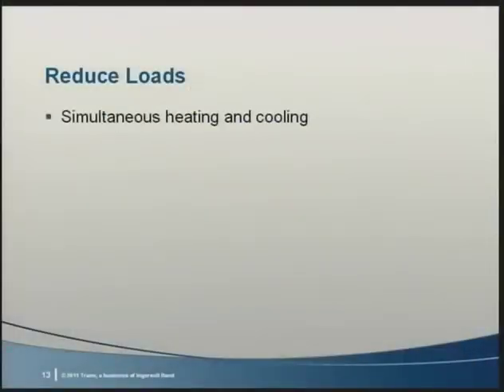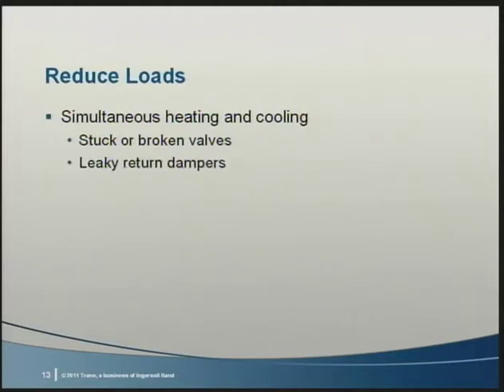Simultaneous heating and cooling is often one reason why a building blows its HVAC budget. When spaces are comfortable, this energy waste can be overlooked. One hidden simultaneous heating and cooling happens because of stuck or broken heating valves. They put additional heat into a space that might now need cooling and might even convert a system from one mode to the other. Leaking return air dampers can add a lot to the cooling or heating coil loads.